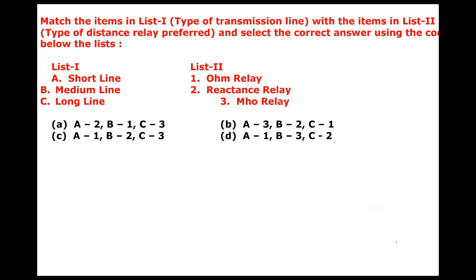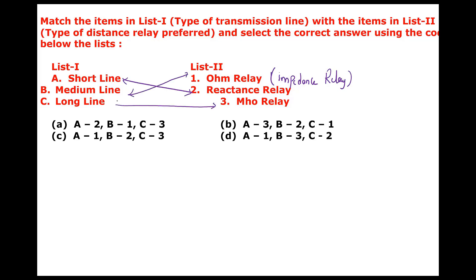For short transmission lines we use reactance relay. For medium transmission lines we use impedance relay, also called ohm relay — both are the same. For medium transmission lines, impedance relay is used. For long transmission lines, Mho relay is used.